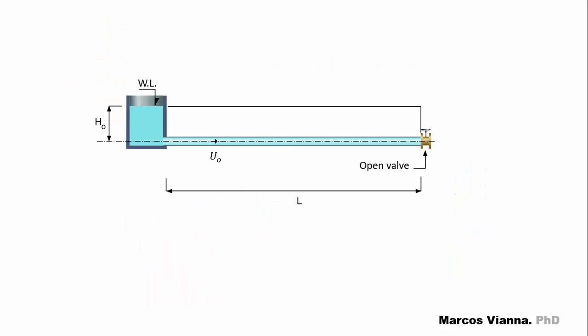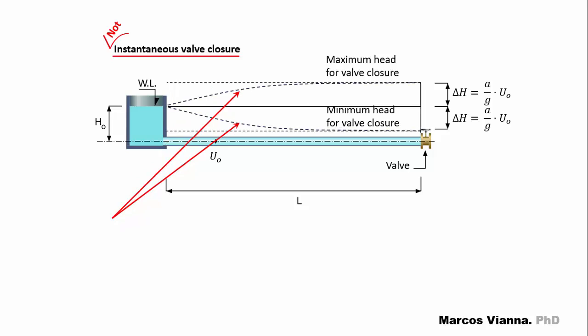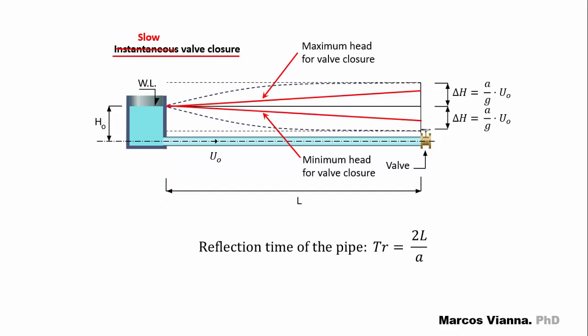When water flows in an installation like this, if the valve is closed instantaneously, the transient pressures, or transient heads, will start to form. If we close the valve more slowly, we can alleviate these transient pressures in a certain extension of the pipeline. But if we close the valve in a time greater than 2L over A — called the reflection time of the pipe — we can alleviate the transient pressures even more. In that case, we say that we have a slow closure situation.